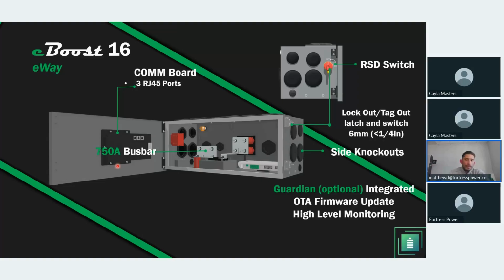It's not a BMU. As I mentioned before, the BMS is integrated within the battery module. This is just to pair all communications together from battery to battery and then battery to inverter. Then you have the side disconnect, which serves as a rapid shutdown switch. For NEC code, they are mandating that not only PV is de-energized, but that your entire system is de-energized: your inverter's AC output, your PV, and your battery's voltage output. And that enhances a safety factor.